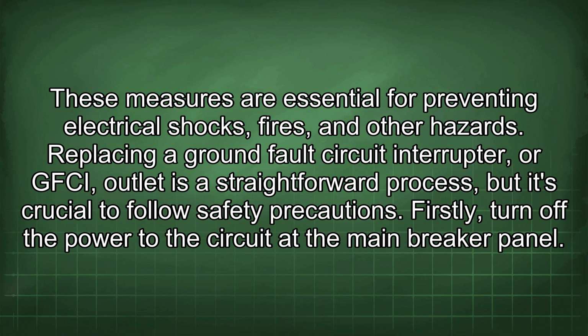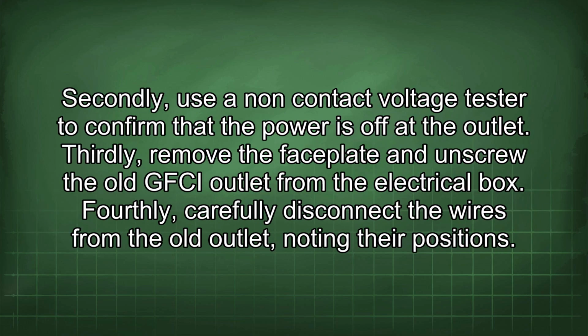Replacing a ground fault circuit interrupter, or GFCI, outlet is a straightforward process, but it's crucial to follow safety precautions. Firstly, turn off the power to the circuit at the main breaker panel. Secondly, use a non-contact voltage tester to confirm that the power is off at the outlet. Thirdly, remove the faceplate and unscrew the old GFCI outlet from the electrical box. Fourthly, carefully disconnect the wires from the old outlet, noting their positions.